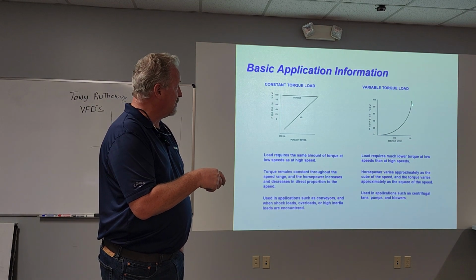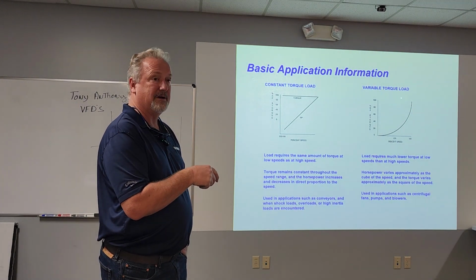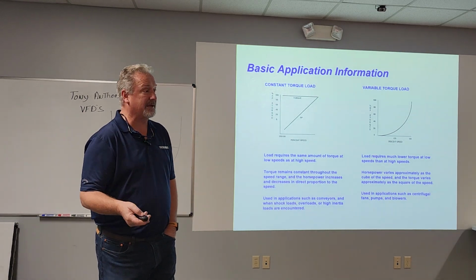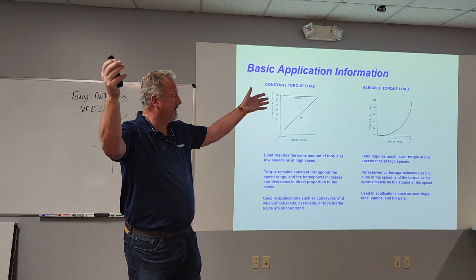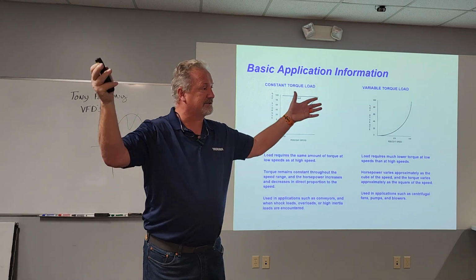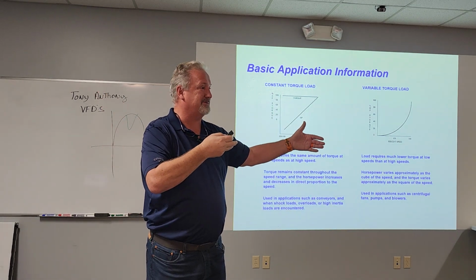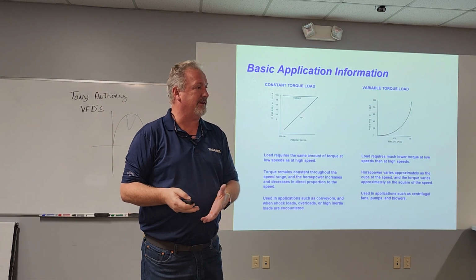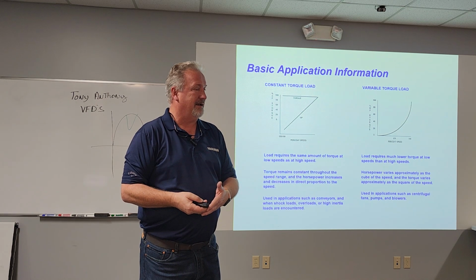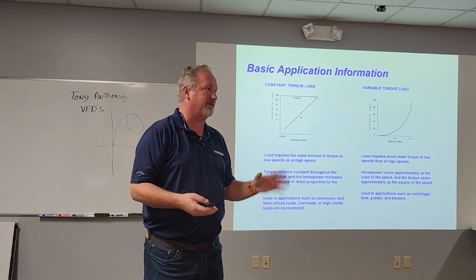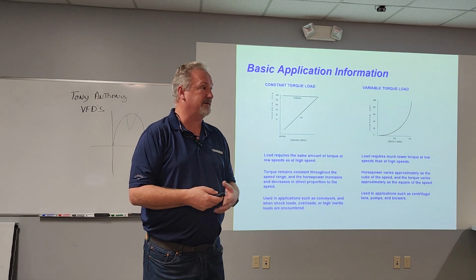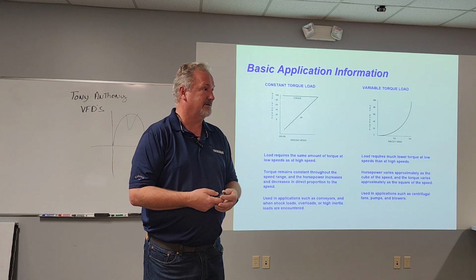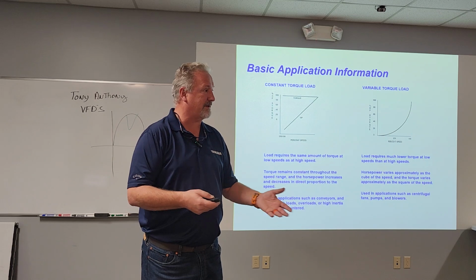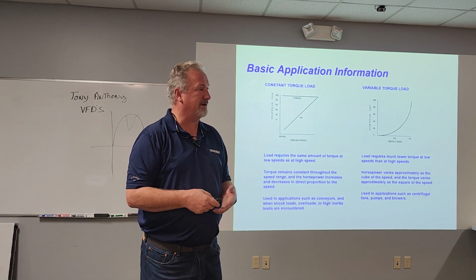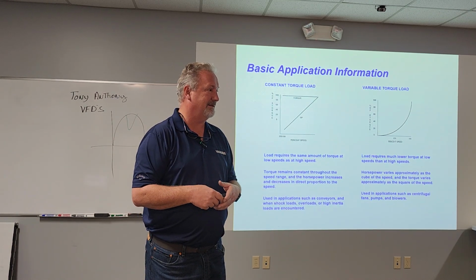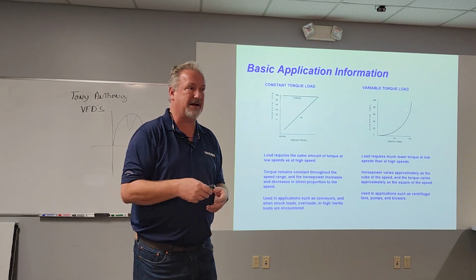So this is where we save all the money, and this is why we have drives on everything out there. Think about that. If you've got an air system and you can slow it down to 48 hertz from 60, you cut the energy required to run that motor in half. A 10 horse motor, if it's running 24/7, which most of them aren't, costs around $10,000 to $15,000 a year to run. So if you run it 8 hours a day, it's still going to be several thousand dollars a year for a 10 horse drive that costs a couple thousand dollars. It doesn't take long to pay for that drive if you can slow it down.